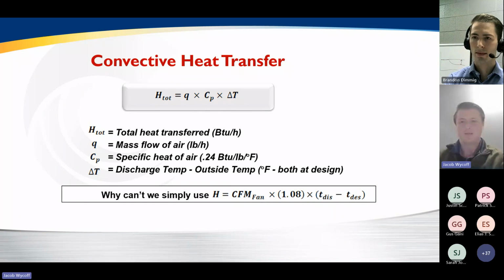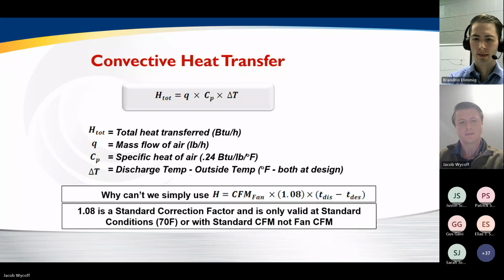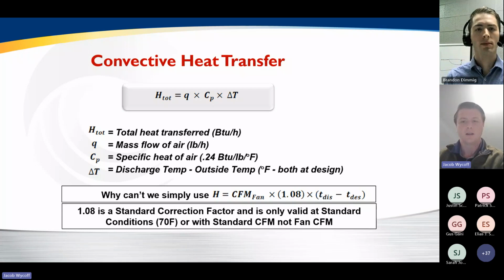And why can't we simply use this? Why isn't this correct 100% of the time? That 1.08 is a standard correction factor that's only going to be valid at standard conditions, which is 70 degrees and sea level. What that 1.08 is trying to do is relate volumetric CFM into mass flow of air times the specific heat of air.